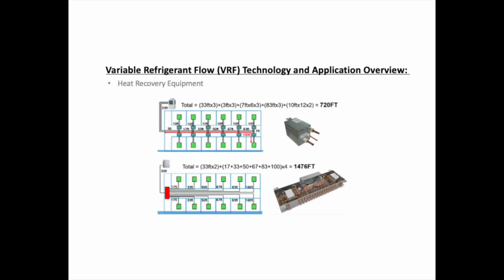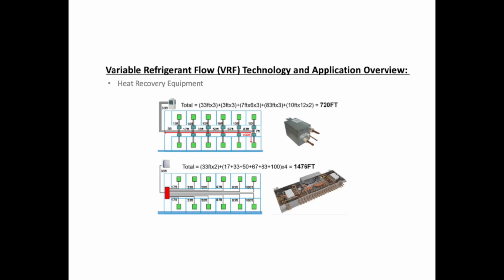And it's important to know which system would be the best candidate for which type of heat recovery system, either 2-pipe or 3-pipe. So you can see in the slide below, depending on the type of system and the layout of the building, you can see that one system is more beneficial than the other system. In this example, using a 2-pipe system and having the big multi-port distribution controller on one end of the building is not the best use of that system, because you have multiple refrigerant lines basically home running to the same area. So there's a lot of redundant refrigerant piping, to where if you used a 3-pipe heat recovery system with multi-port boxes, you can strategically install those flow selector boxes where they need to go and reduce the amount of piping and labor to install those.